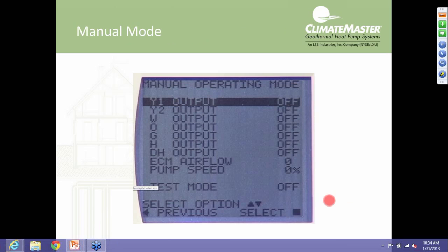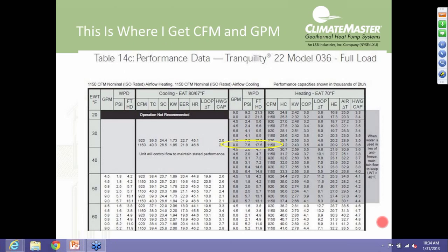Now, in the back of every one of the installation manuals for the digital products, we now have the specification pages for full load operation for the particular model that installation manual is for. For instance, this is a TZ 036 here, the Tranquility 22 model, and I got it highlighted here in yellow or circled in yellow. If we had 30-degree entering water looking over here, skipping on across, we're in the heating mode.